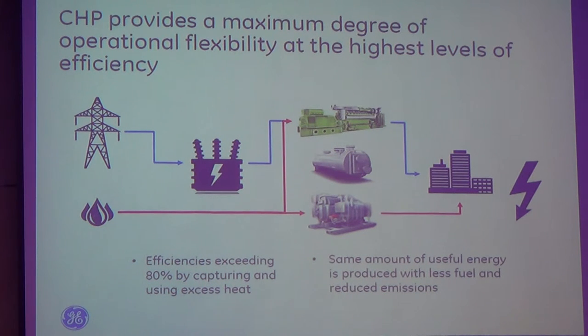In the absorption chiller, when you put in exhaust heat around 400 degrees Celsius, there are two parameters: the flow and the temperature of the exhaust heat. When you put in room temperature water, it comes out of the chiller at 7 degrees Celsius, so it can be used for cooling buildings or data centers.